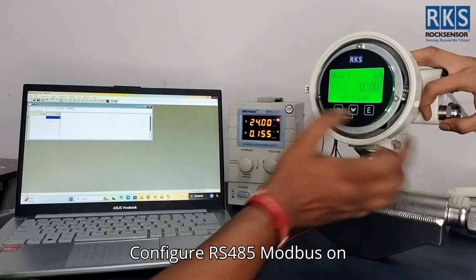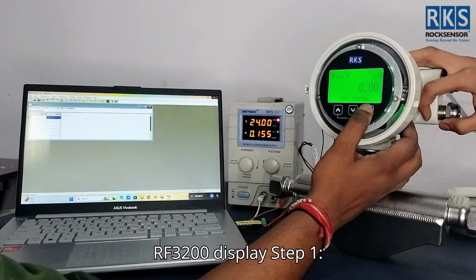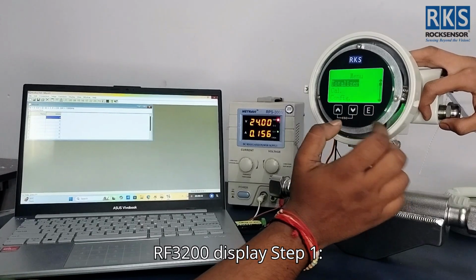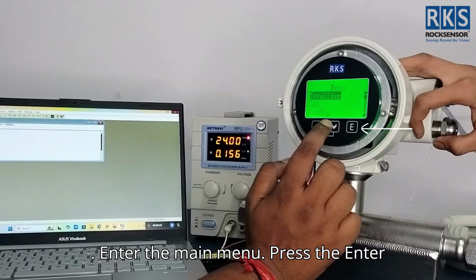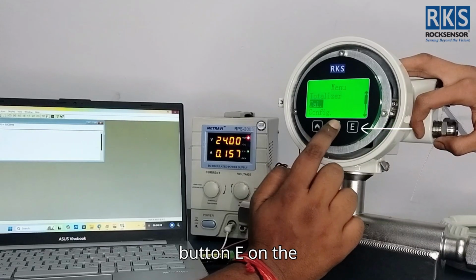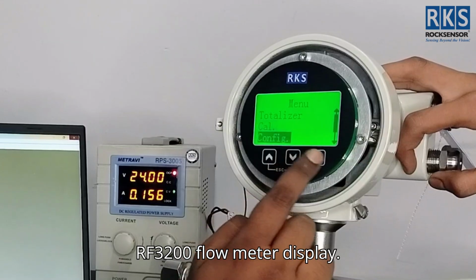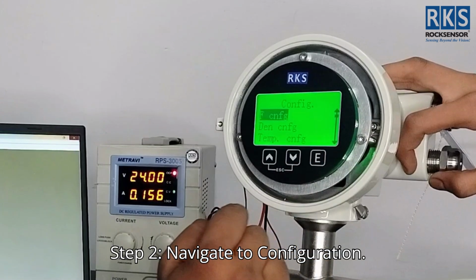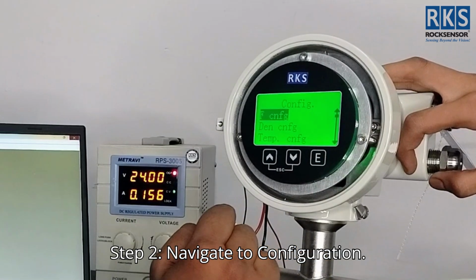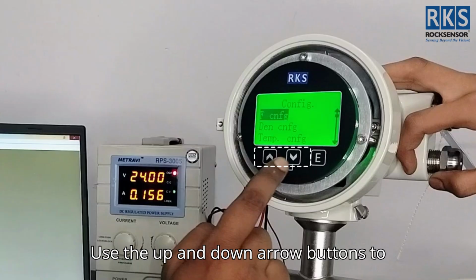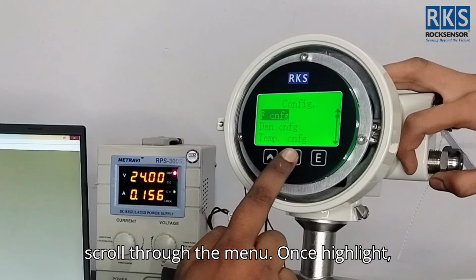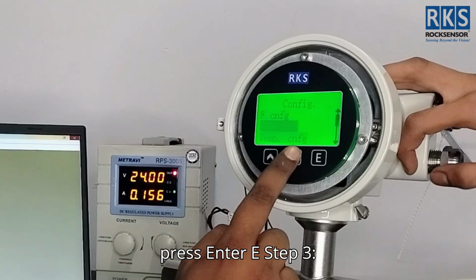Configure RS485 MODBUS on RF3200 display. Step 1. Enter the main menu. Press the Enter button, E, on the RF3200 Flowmeter display. Step 2. Navigate to configuration. Use the up and down arrow buttons to scroll through the menu. Once highlighted, press Enter, E.